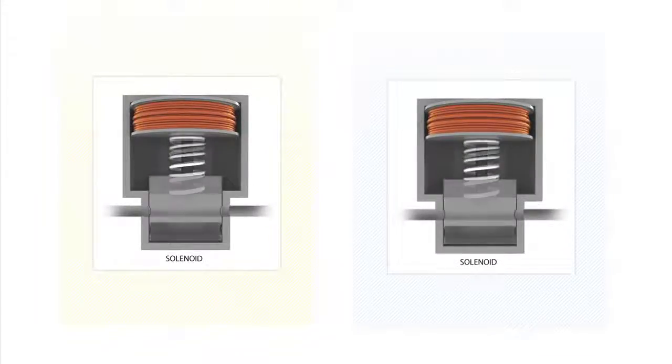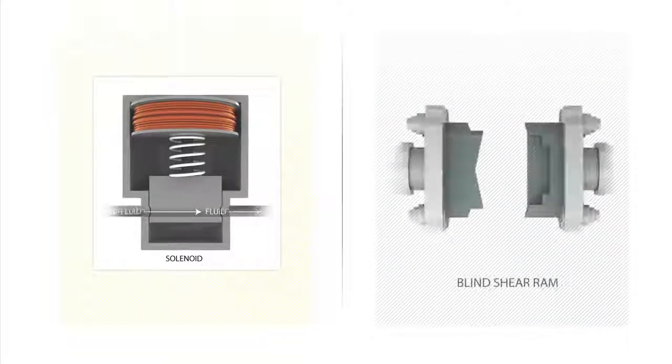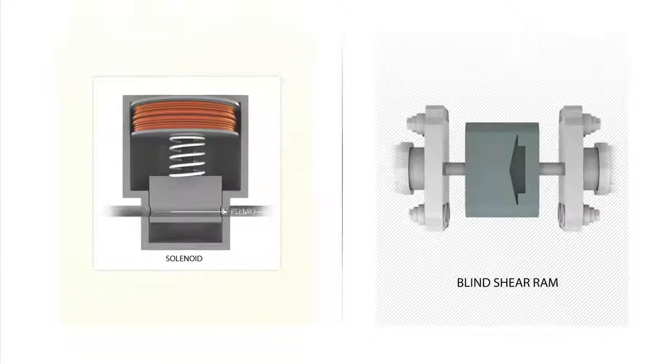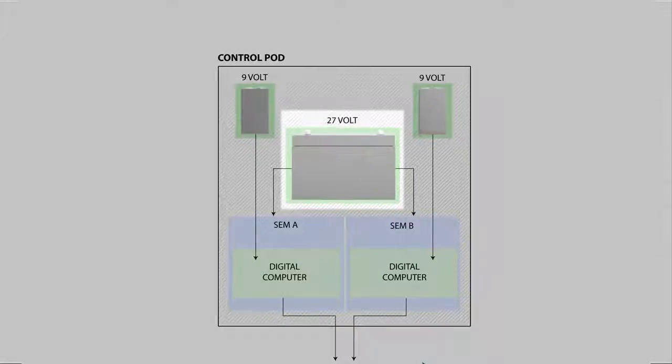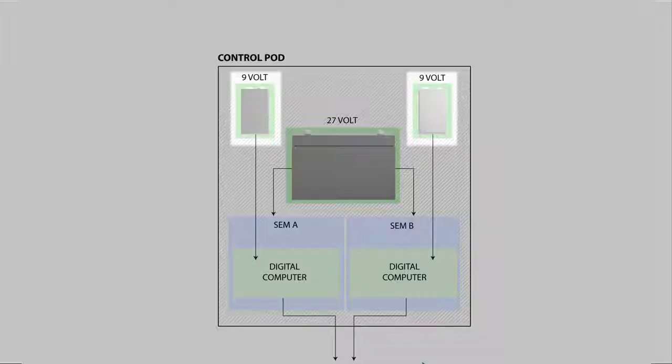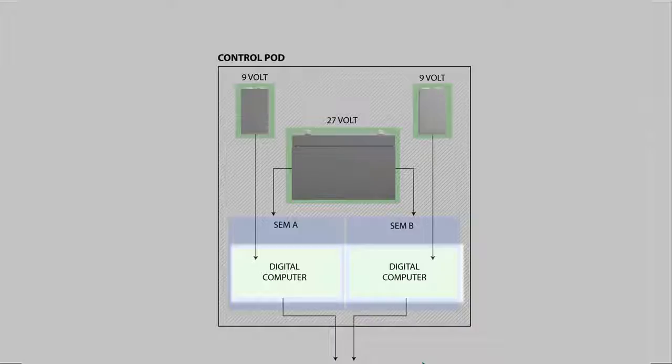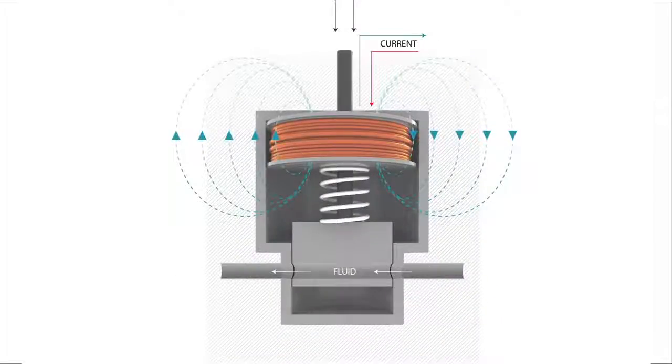When activated, the solenoid valves controlled important BOP functions, such as closing the blind shear ram. If electrical power from the rig was lost, as happened on April 20, 2010, both the Yellow and Blue control pods contained backup twenty-seven-volt and nine-volt batteries to power emergency functions. The nine-volt batteries powered computers that would activate the solenoid valves, which were powered by the twenty-seven-volt batteries.